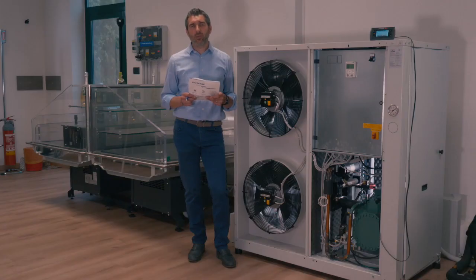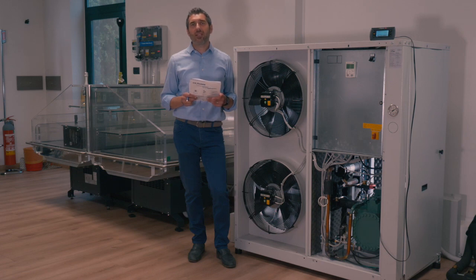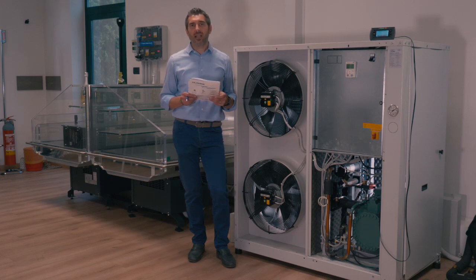The low temperature units are also called open flash tanks because they do not have a flash valve. The temperature and pressure of the receiver varies autonomously according to the system operating conditions, outside temperature and evaporation pressure.